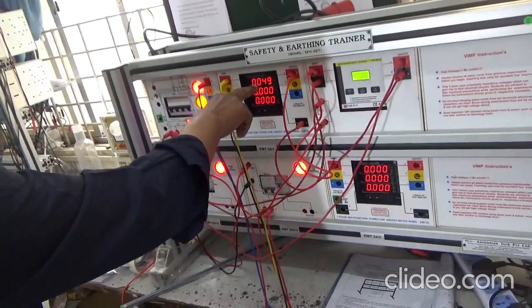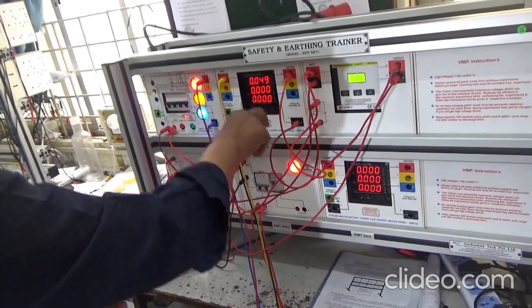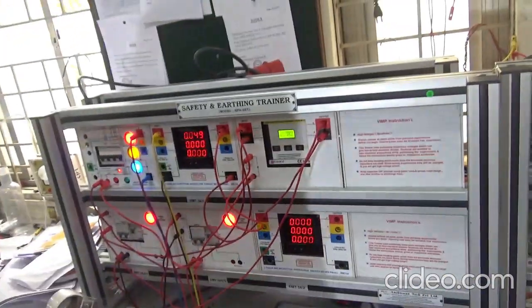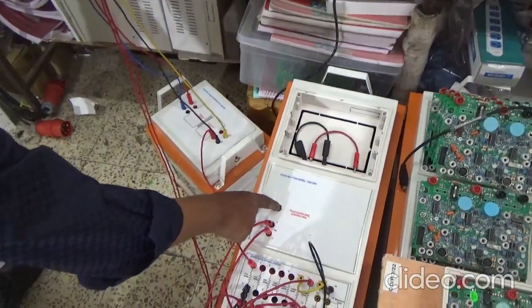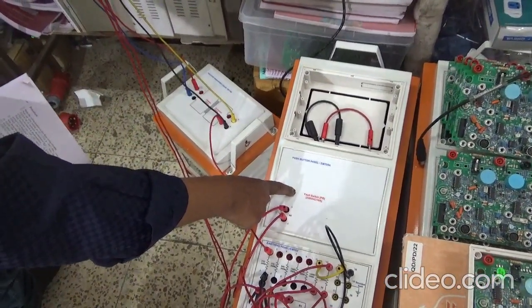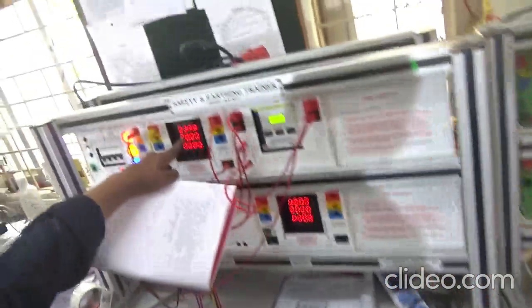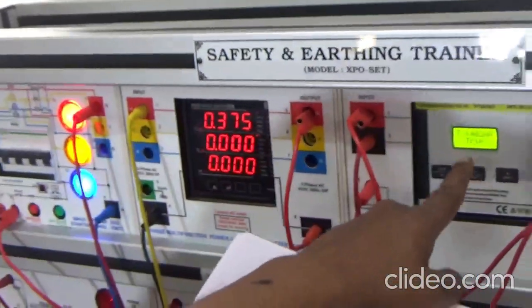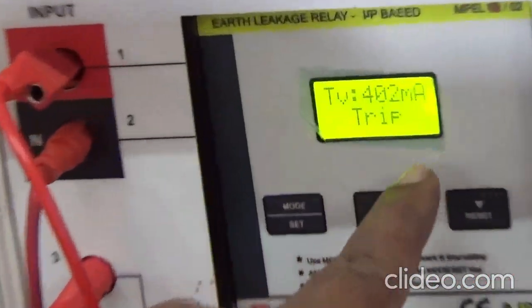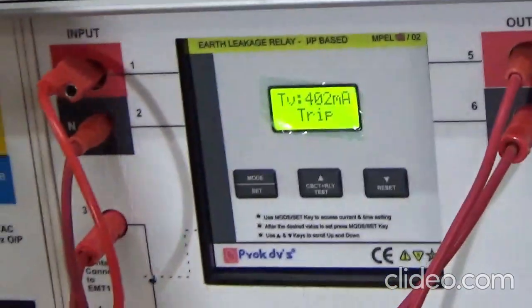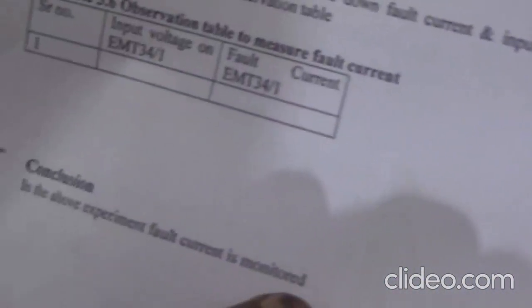Right now it is 0.049 ampere, that is milliampere. I'll press it. Please see fault switch push button. I'll have to press it for a few seconds. I have started pressing it. The current has increased to 0.398. Immediately it has tripped. It has tripped at 402 milliampere. So the conclusion is that in the above experiment, fault current is monitored. This is the conclusion of this simple experiment, that is measurement of fault current.